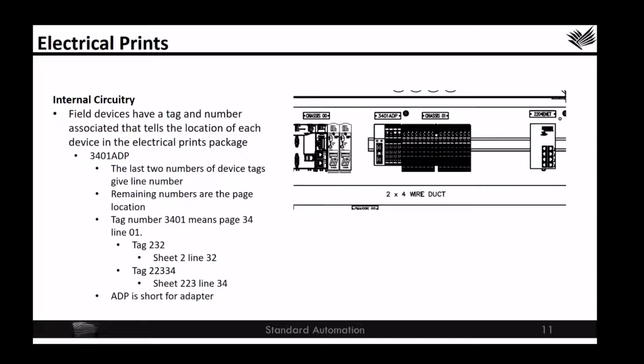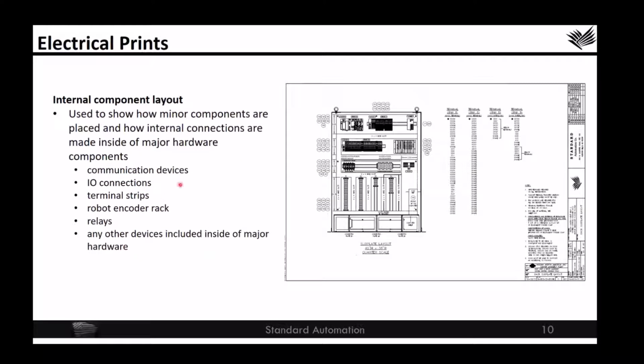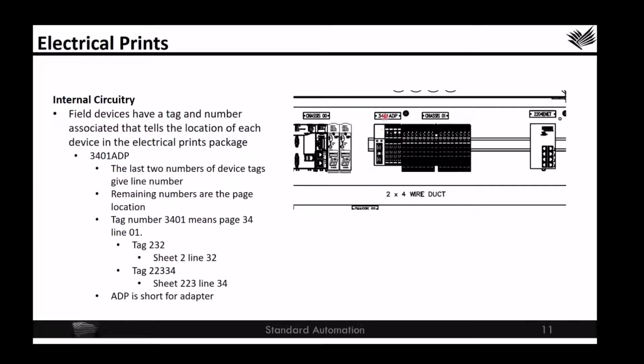As part of the internal circuitry, the field device tags and tag numbers are shown in the layout. If we zoom in on the top area of the robot of the SCC layout, shown in this diagram, we can see that the device tag for chassis 1 is 3401 ADP. Now, that 3401 ADP designation has meaning.